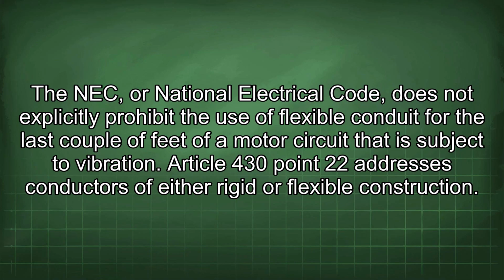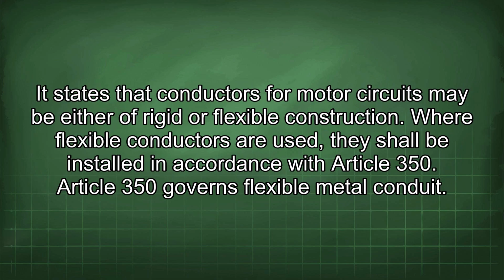The NEC, or National Electrical Code, does not explicitly prohibit the use of flexible conduit for the last couple of feet of a motor circuit that is subject to vibration. Article 430.22 addresses conductors of either rigid or flexible construction. It states that conductors for motor circuits may be either of rigid or flexible construction. Where flexible conductors are used, they shall be installed in accordance with Article 350. Article 350 governs flexible metal conduit.